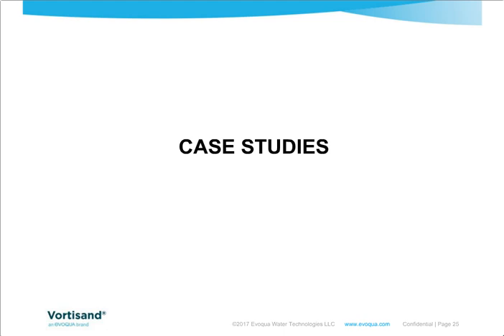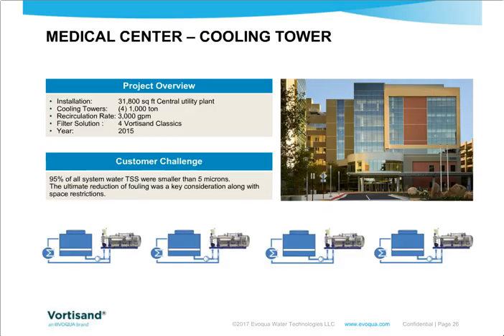Now we're going to go into some of the case studies, the number of installations that this high efficiency micro sand filtration has been installed on. Firstly, let's look at a medical center, a large hospital that installed a large central utility plant. They had 4 1,000-ton cooling towers, each at a circulation rate of 3,000 GPM. 4 VortiSand Classic filters were installed back in 2015. And really the challenge here was that the majority, or 95%, of the TSS in the water was less than 5 microns. It indicated that they needed fine filtration.